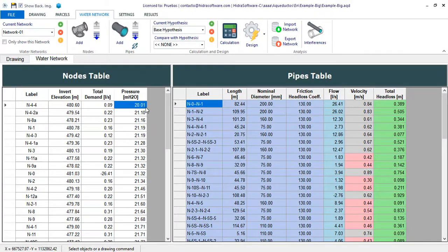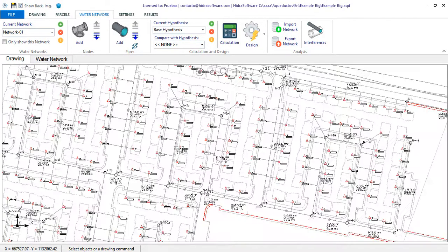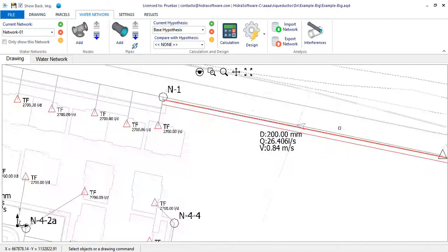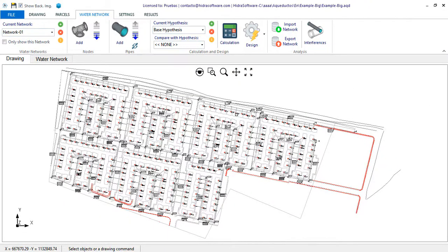Now let's suppose that within your system's analysis and design it is required to evaluate what will happen to the water distribution network when its pipes, let's suppose they're metallic, become older in terms of their friction coefficient. That is, you are interested in knowing, since the maximum flow will be the same for the area of influence of the network, which should be, after 10 or 15 years, the piezometric head that must guarantee the system's source to maintain the normative minimum pressure of 20 meters.